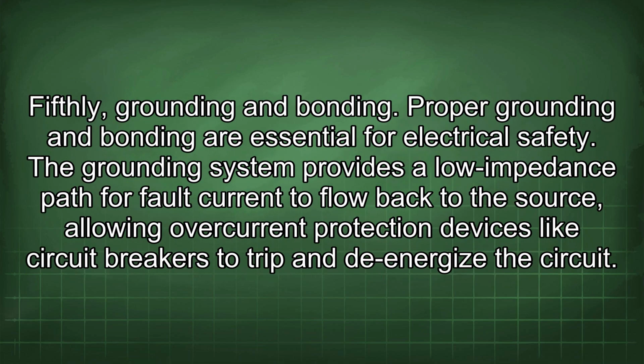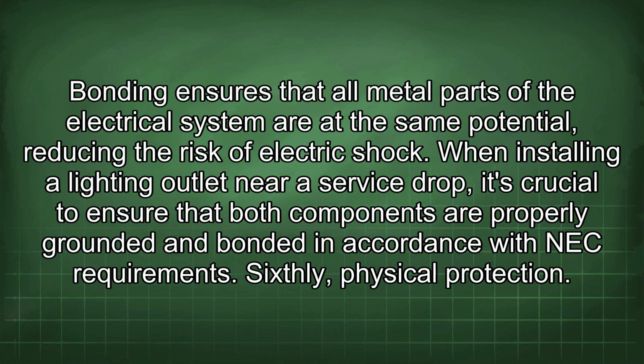Fifthly, grounding and bonding. Proper grounding and bonding are essential for electrical safety. The grounding system provides a low impedance path for fault current to flow back to the source, allowing overcurrent protection devices like circuit breakers to trip and de-energize the circuit. Bonding ensures that all metal parts of the electrical system are at the same potential, reducing the risk of electric shock. When installing a lighting outlet near a service drop, it's crucial to ensure that both components are properly grounded and bonded in accordance with NEC requirements.